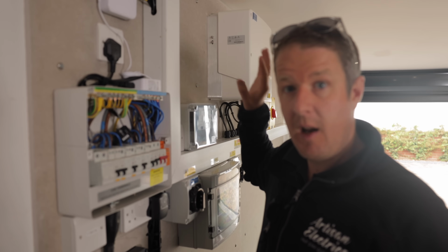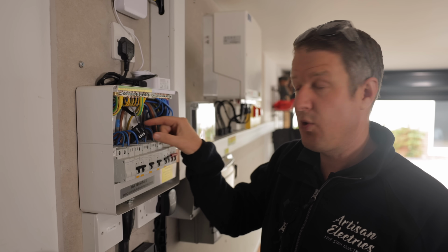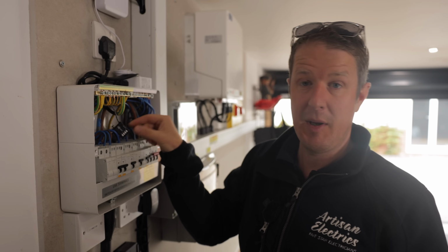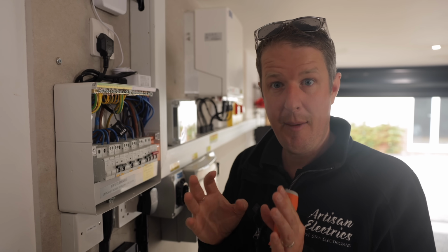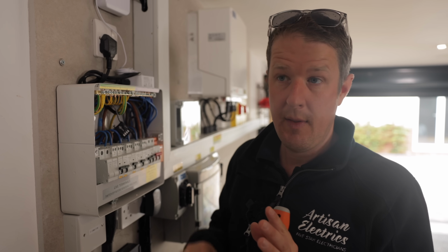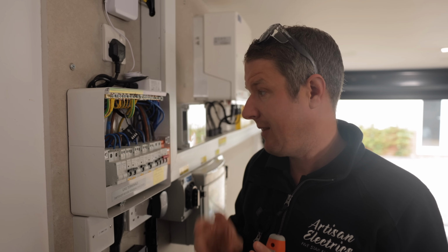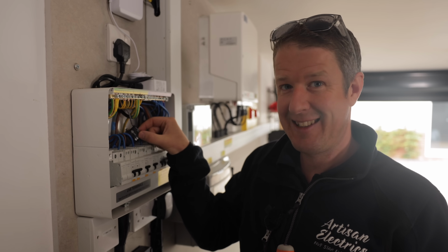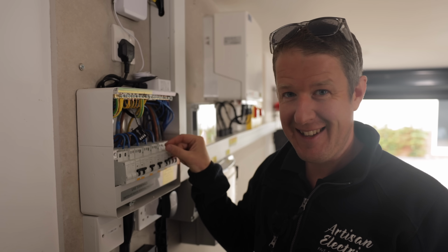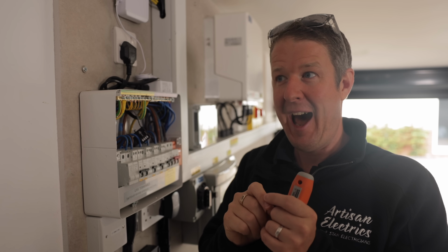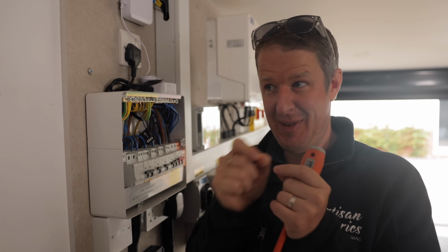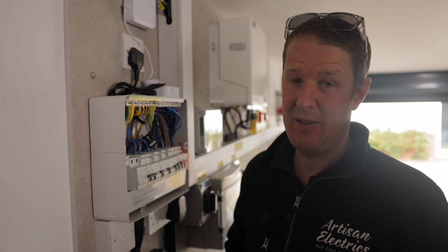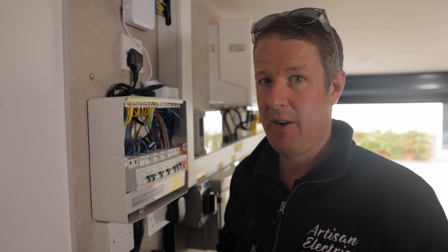If you're connecting the solar PV directly into the Libbi inverter, you do not need a solar CT, because the Libbi controller reads how much solar is being generated through the hybrid inverter. That's a little thing to note. If you do add a separate solar CT onto the Libbi circuit, it gets confused and shows 2 solar arrays when there's only one. So don't install a solar CT if you're connecting the solar directly into the Libbi.